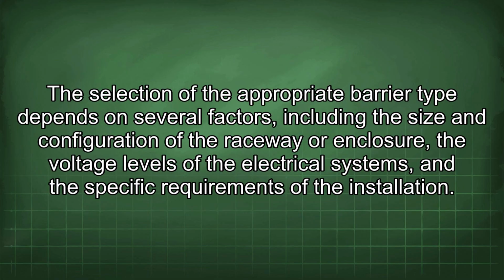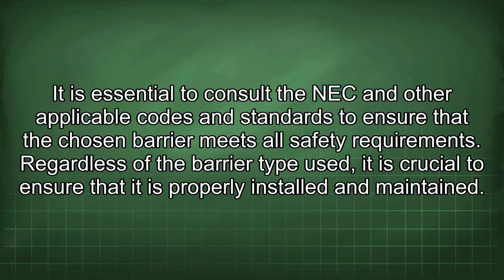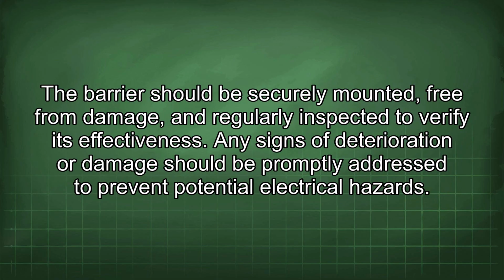The selection of the appropriate barrier type depends on several factors, including the size and configuration of the raceway or enclosure, the voltage levels of the electrical systems, and the specific requirements of the installation. It is essential to consult the NEC and other applicable codes and standards to ensure that the chosen barrier meets all safety requirements. Regardless of the barrier type used, it is crucial to ensure that it is properly installed and maintained. The barrier should be securely mounted, free from damage, and regularly inspected to verify its effectiveness. Any signs of deterioration or damage should be promptly addressed to prevent potential electrical hazards.